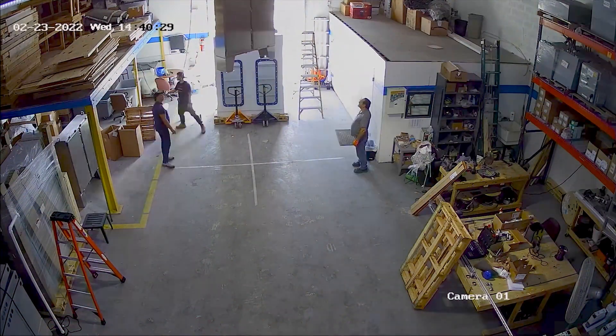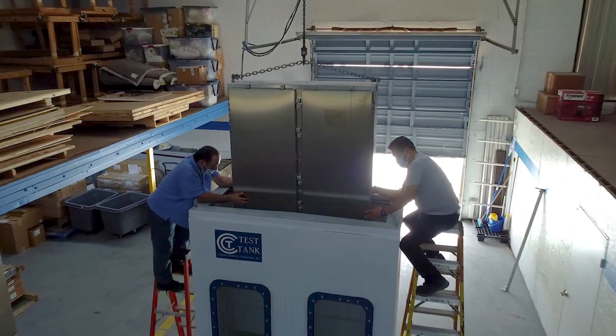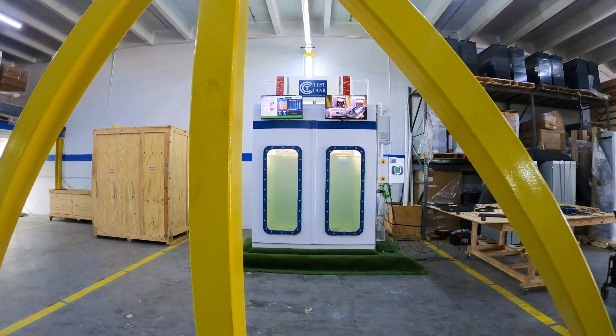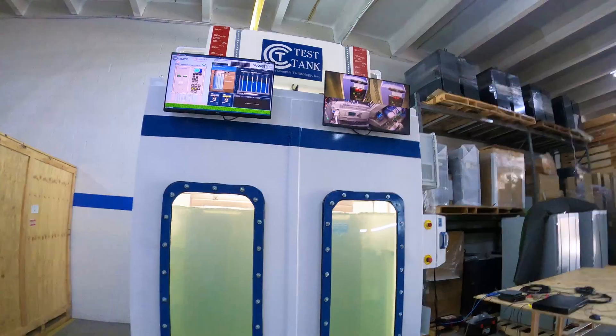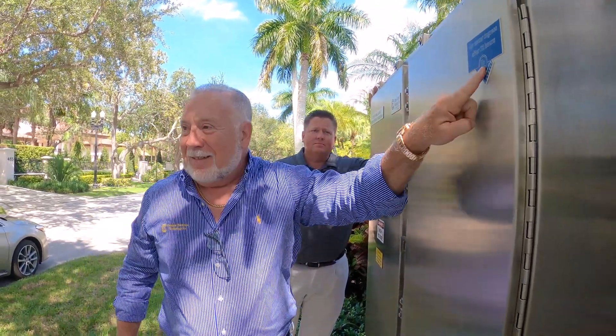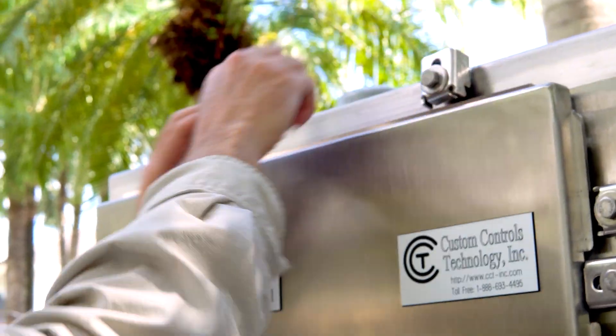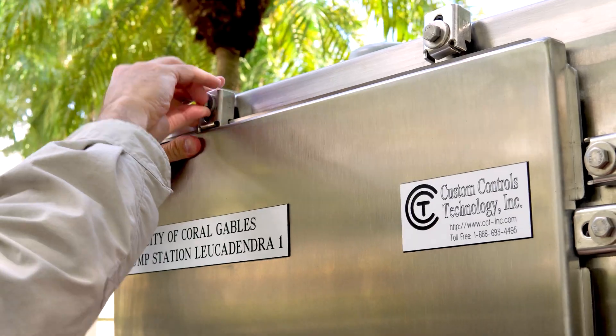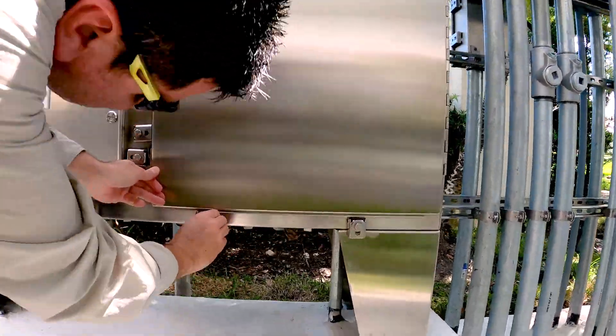I had the idea of improving a NEMA 4X rated enclosure to be resilient to floods. It is validated by UL that the system is submersible 72 hours under 10 inches above the enclosure. The opening and closing of this enclosure is very simple — very few bolts, no torquing required. It bottoms out and you're done. The City of Coral Gables is the first municipality to implement the system.